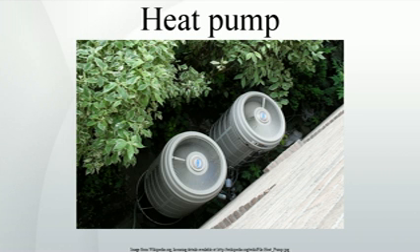Ultimately, due to Carnot efficiency limits, the heat pump's performance will approach 1.0 as the outdoor to indoor temperature difference increases for colder climates, as the outside temperature gets colder. This typically occurs around −18 °C, 0 °F, outdoor temperature for air source heat pumps.